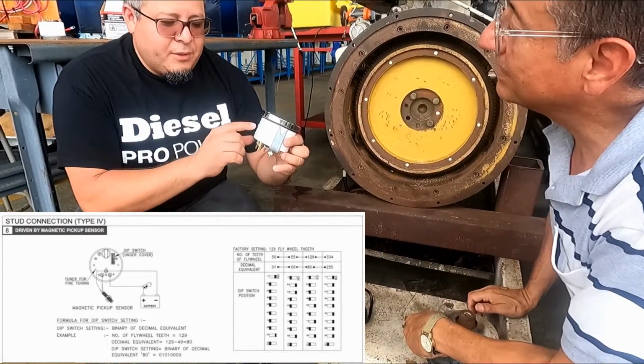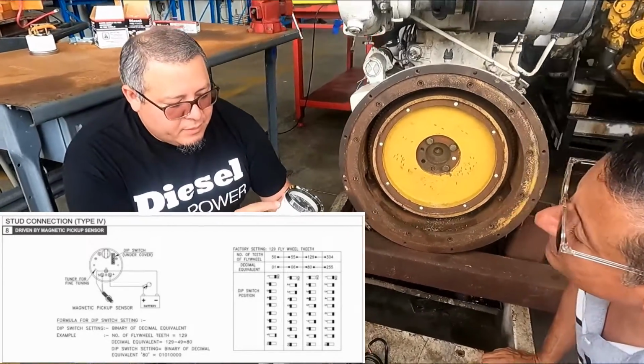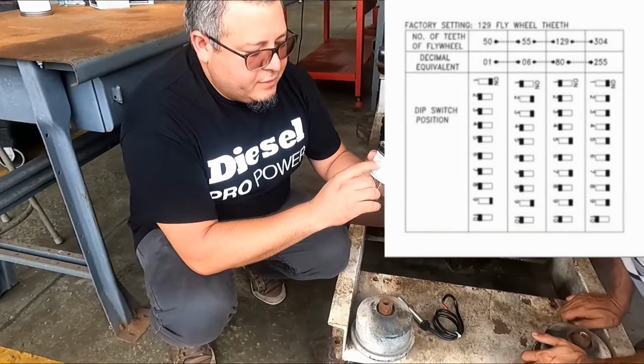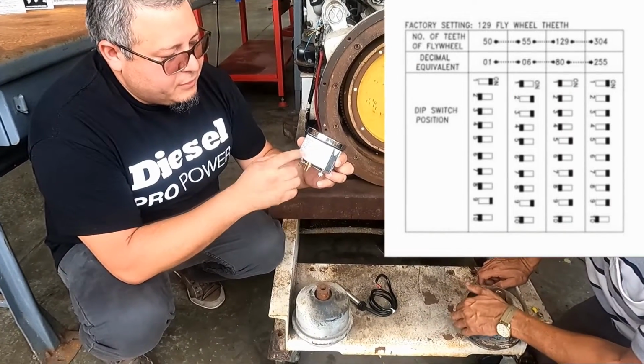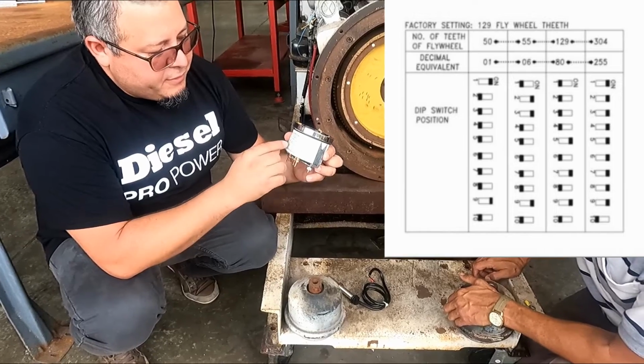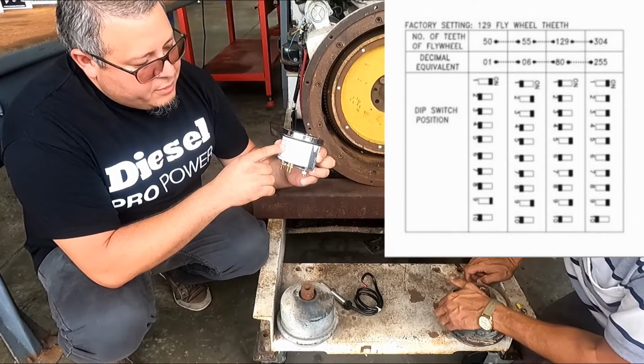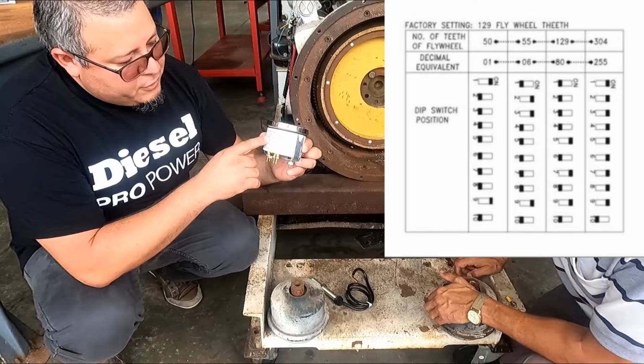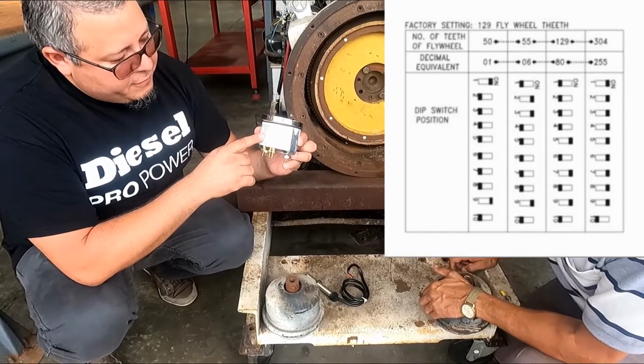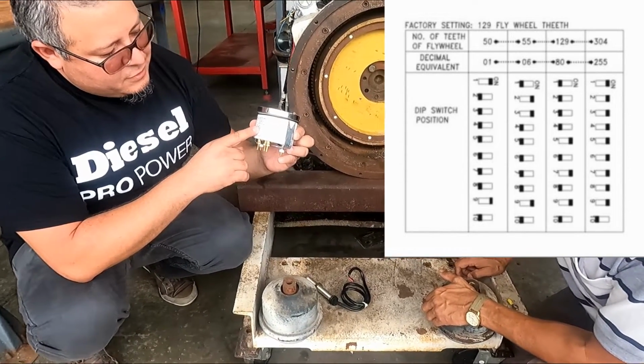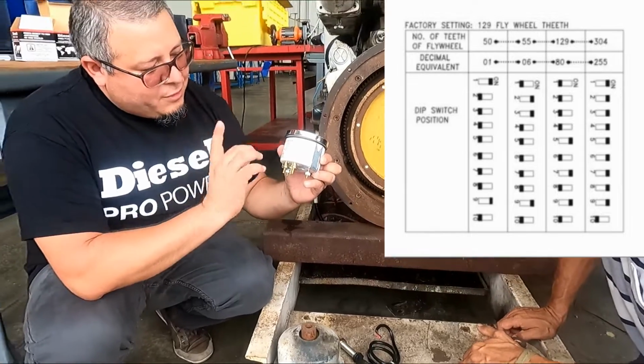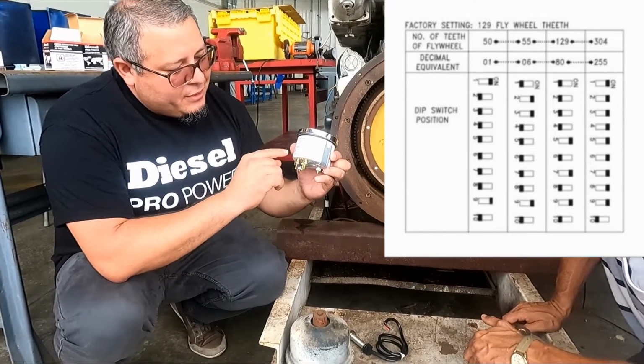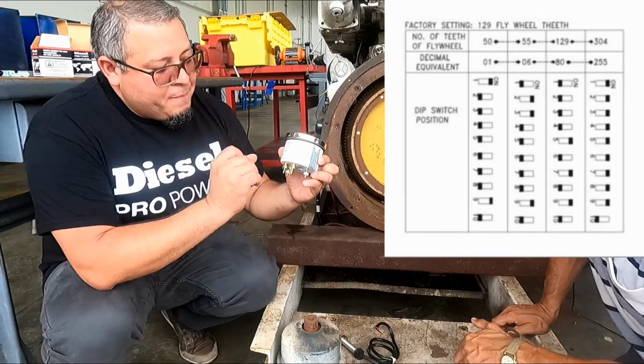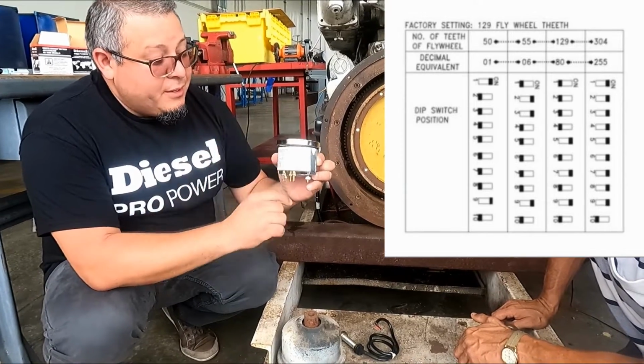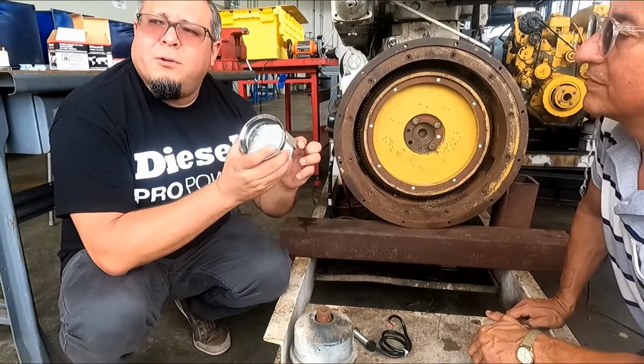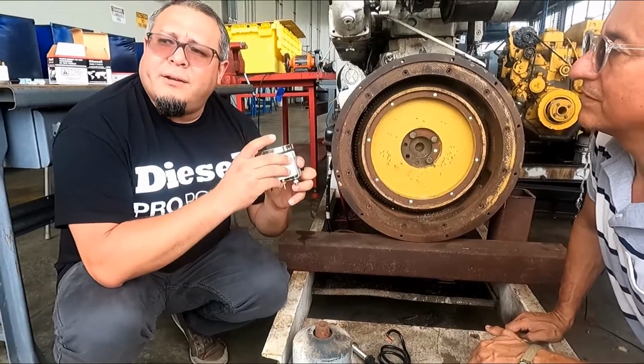This little table, for example, says 50 teeth. So if your flywheel has 50 teeth, from 50 to 55, dip switch number 1 you put on, switches 2, 3, 4, and 5 off, 6, 7, and 8 off, then turn on number 9, and number 10 off. That way the tachometer will read the correct pulses and correct RPMs of the engine.